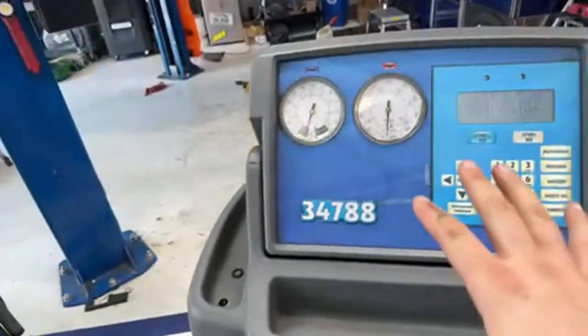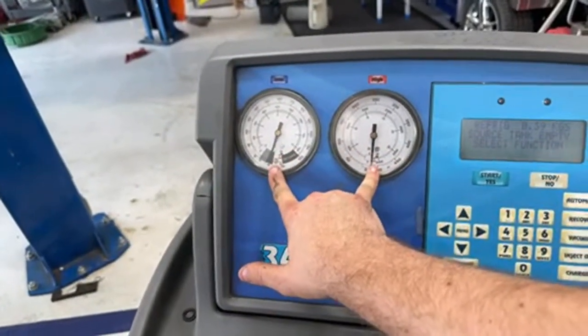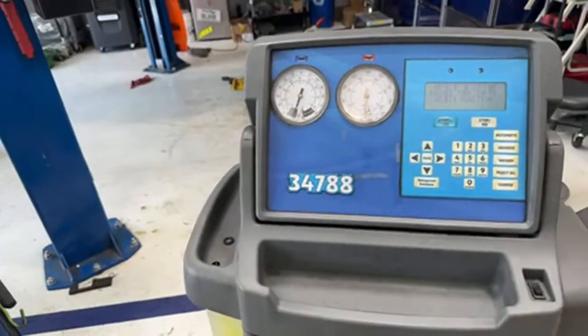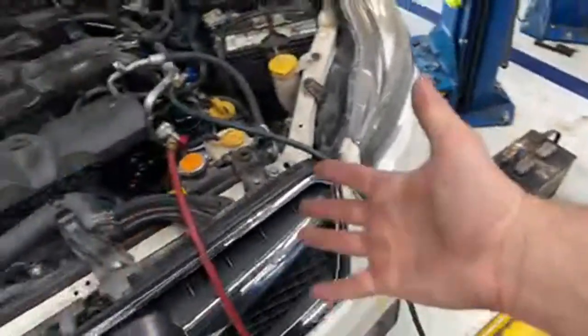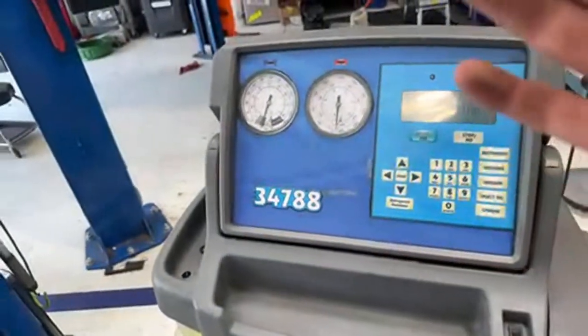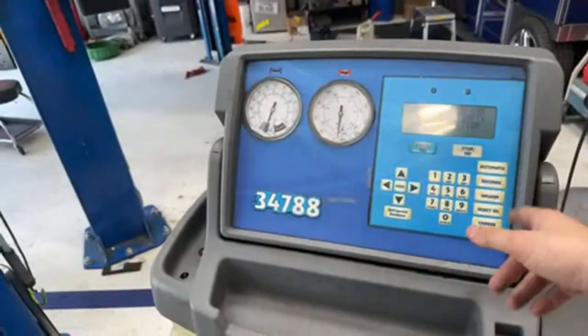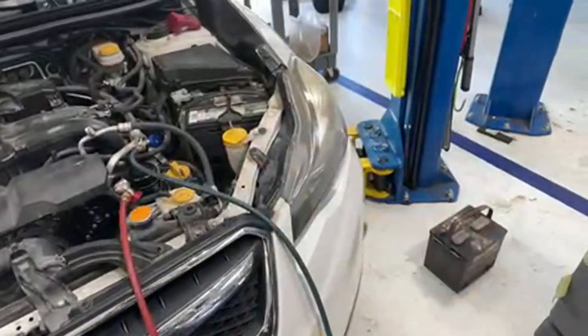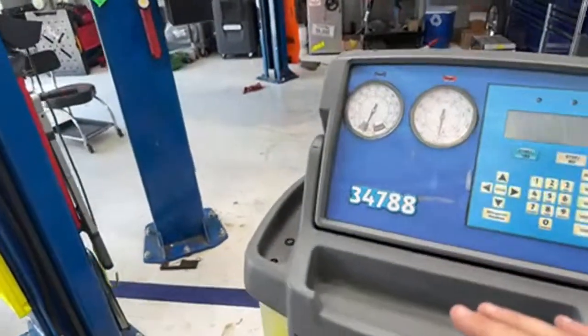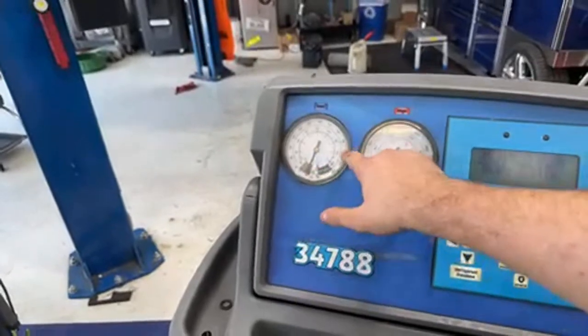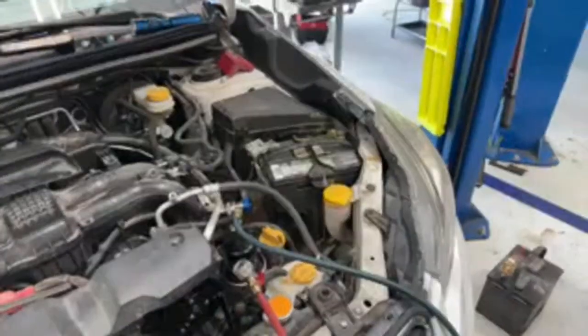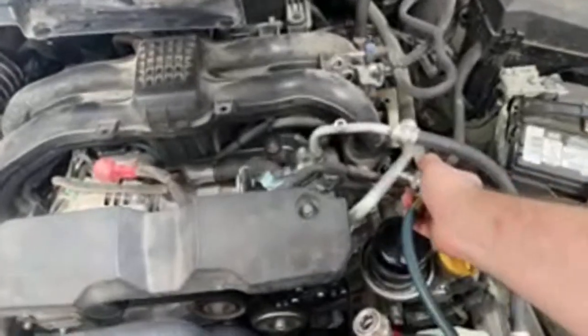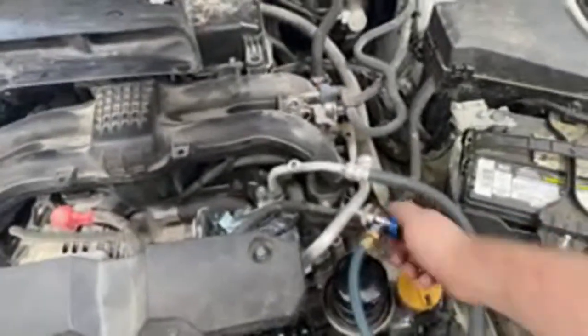An important note: make sure your gauges are on the low setting. That means when somebody was done using the AC machine, the lines were recovered appropriately. If it was any different, you'll want to run a recovery cycle to make sure there's nothing in the lines, because I've had technicians forget to check this, and these lines were holding about 100 psi of charge. That means there's freon in these lines, and if that freon gets introduced into the system, one, you could contaminate it, and two, you could temporarily fix your problem because you gave it just enough charge to fix itself.